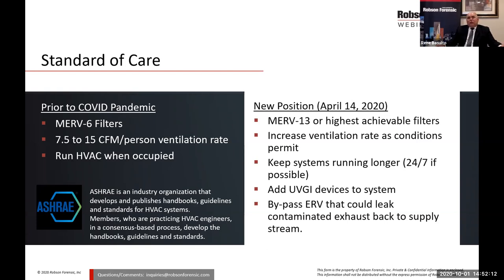So that's one. ASHRAE now is recommending that you increase the ventilation rate as conditions permit. Again, remember the limitations. Equipment will not have sufficient capacity to handle too much of an outside air increase. In the office, I was able to double it because it was significantly reduced at the intake. I was able to open up the intake and it seems to be functioning fine. It's been functioning like this for several months, and when we went through the summer we didn't feel any effect inside the building as far as temperature control. So we were able to increase it significantly.